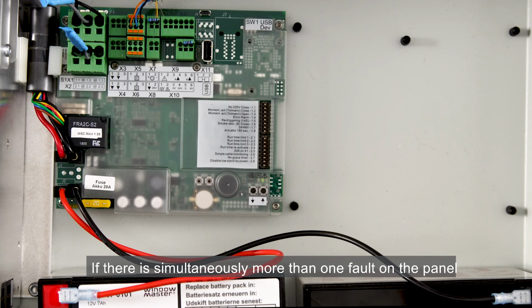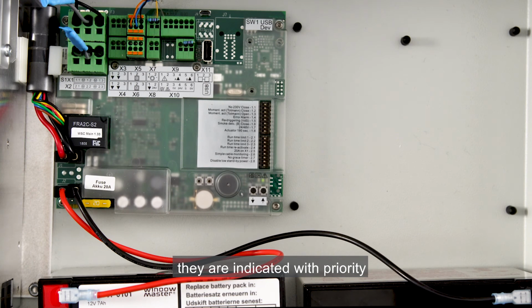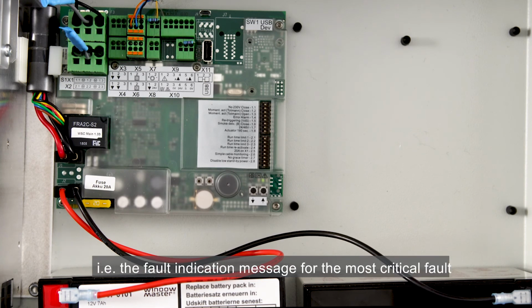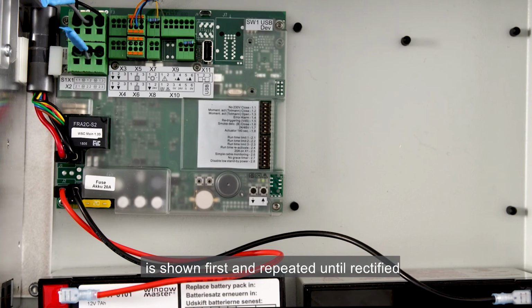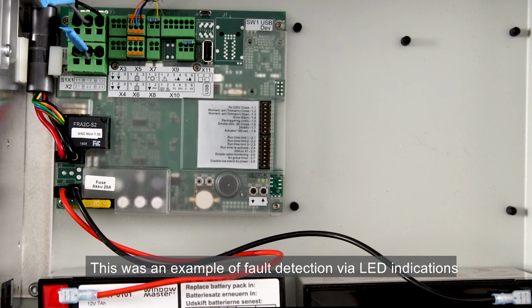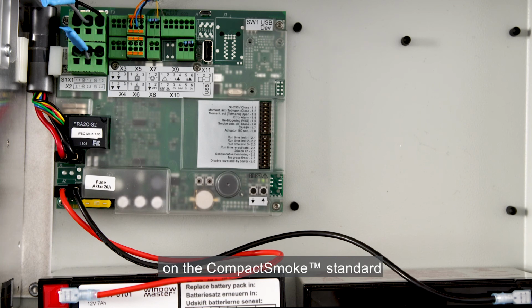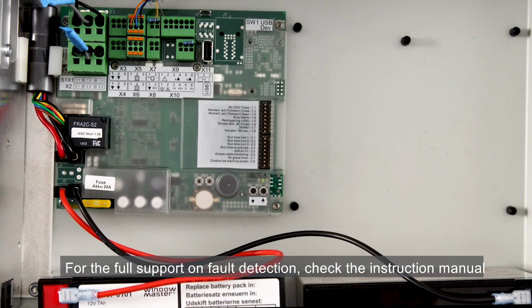If there is simultaneously more than one fault on the panel, they're indicated with priority. That means the fault indication message for the most critical fault is shown first and repeated until rectified. This was an example of fault detection via LED indications on the CompactSmoke Standard. For the full support on fault detection, check the instruction manual.